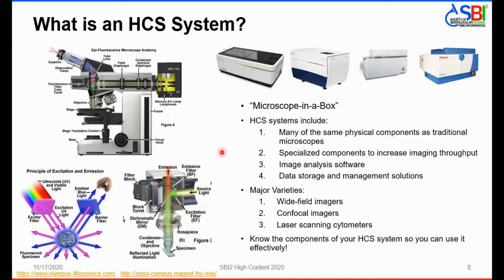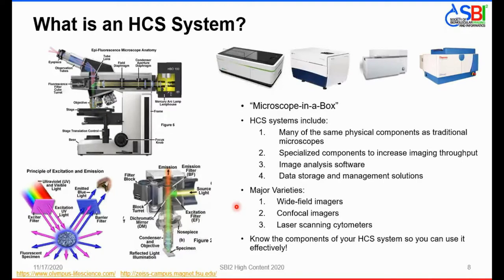What exactly is a high-content screening system? In its simplest terms, it's a microscope in a box. HCS systems include many of the same physical components as traditional microscopes, with specialized components to increase imaging throughput and image analysis software to evaluate images. These instruments also typically come equipped with data storage and data management solutions. There are many varieties of high-content imaging systems, including wide-field imagers, confocal imagers, and laser scanning cytometers. Knowing the components of your HCS system is key to using it effectively.